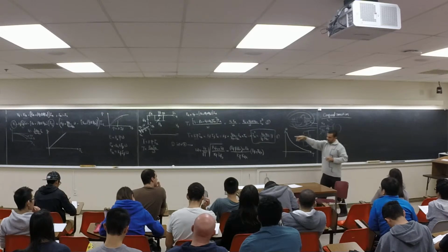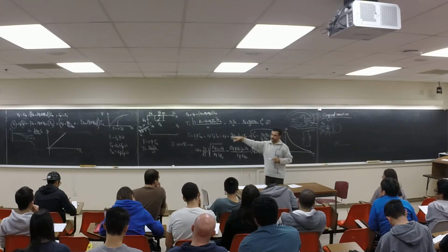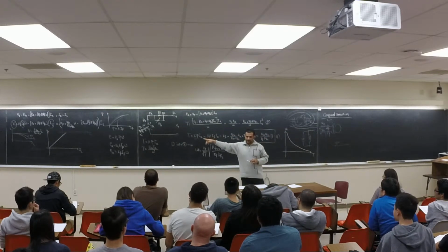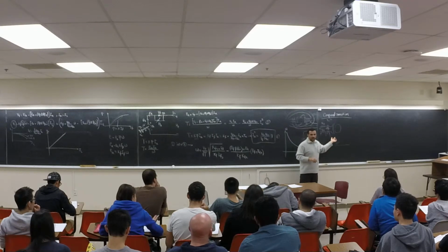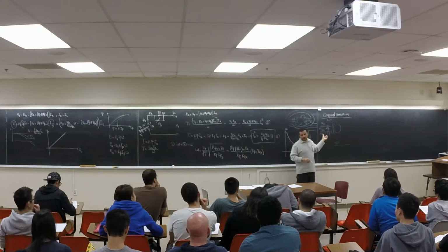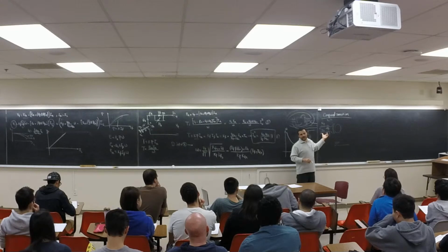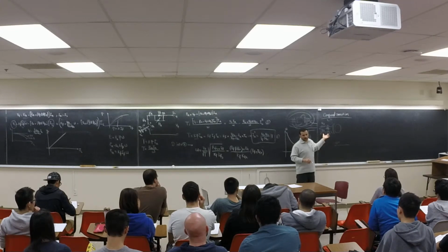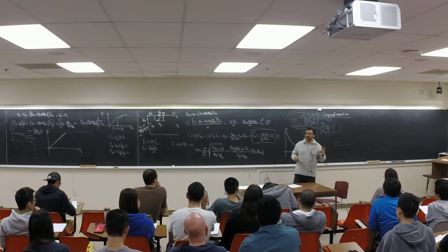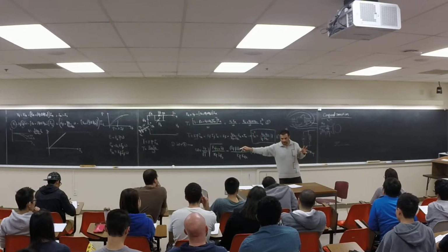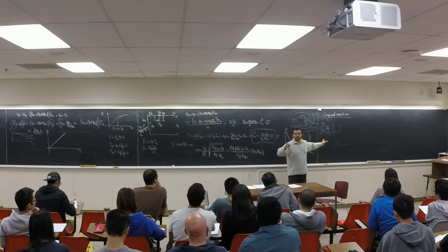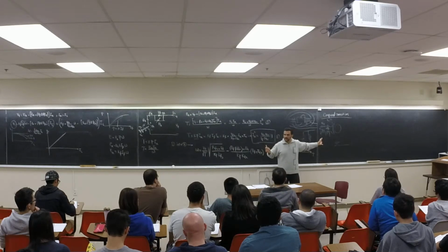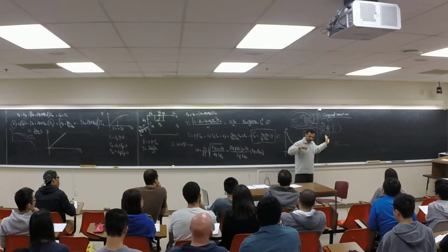So you can see the series machines are not good for the generator. Look at that characteristic over there, it's not good for a generator. So I cannot put just series here. The good ones are either the separately excited or shunt. But the separately excited needs its own excitation system, which is extra money. If I use shunt, I don't need an extra source. I can use the machine itself to support it.